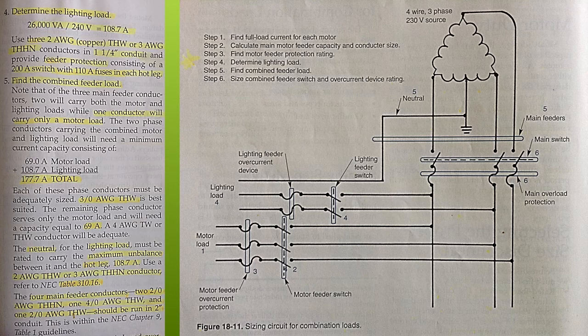Continuing with the steps, step 4, determine the lighting load. We have 26,000 VA divided by 240 volts, which equals 108.7 amps. For this, we use 2 AWG copper THW or 3 AWG THHN conductors in 1.25-inch conduit, and we provide feeder protection consisting of a 200 amp switch with 110 amp fuses in each hot leg, or each current carrying conductor.